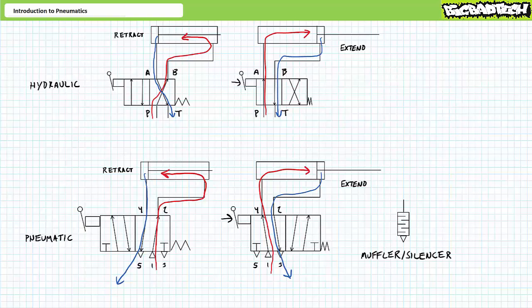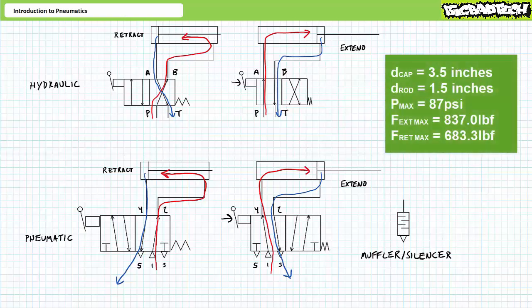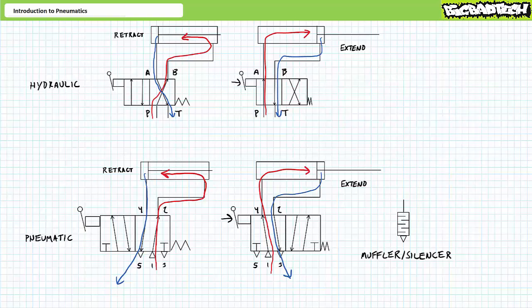Let's discuss how pressure and flow rate influence actuator force and speed for these two different systems. Presuming a cylinder with a cap diameter of three and a half inches, a rod diameter of one and a half inches, and a system capable of producing a maximum pressure of 87 psi, Pascal's law would demonstrate that both systems will extend with 837 pounds force and retract with 683.3 pounds force. Presuming a constant flow rate, extension will be slower and retraction will be faster because extension necessitates a larger cap end volume be filled and retraction uses a smaller tubular rod end volume. In summary, valve position controls actuator direction, pressure controls actuator force, and flow rate determines actuator speed — these fundamental properties remain equally valid for both systems.